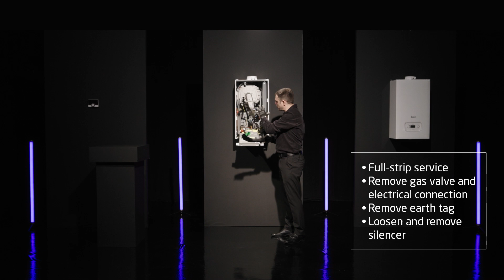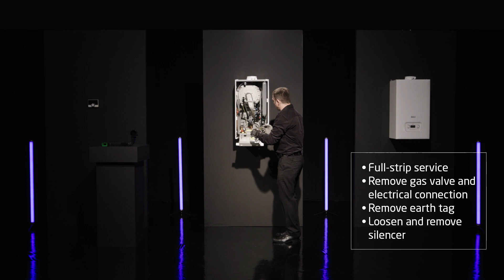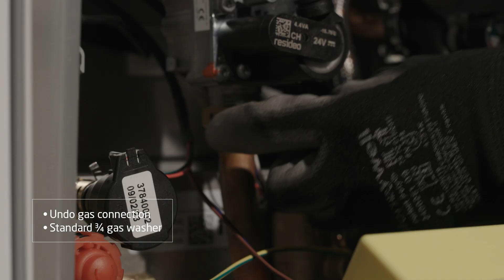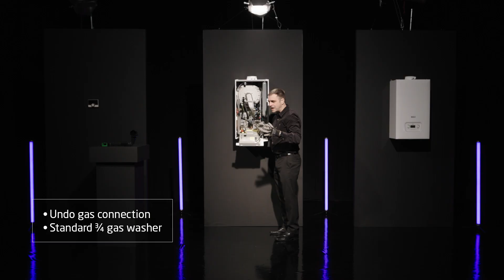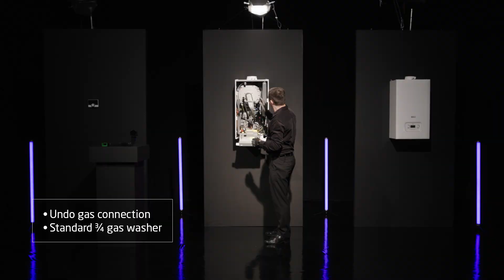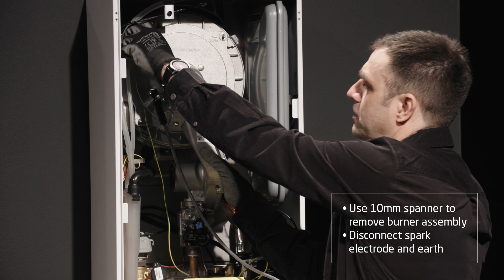And of course this silencer is doing a great job at keeping this boiler really, really quiet. Now what I'm going to do is undo my gas connection, and what you have in there is a standard 3/4 gas washer. So you're going to be carrying that, so you don't have to replace it if you don't need to, but there's nothing to worry about if you do. Then I've got 4 bolts. You can see I've taken a couple of these out already. 10mm spanner, undo these connections, and then I'm ready to take out the burner assembly.